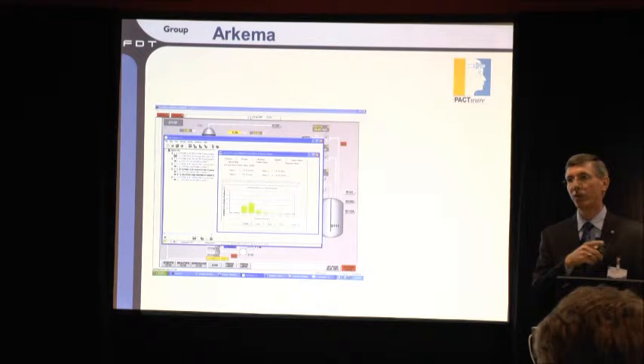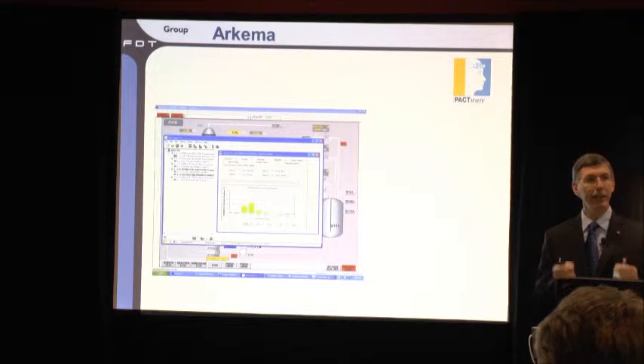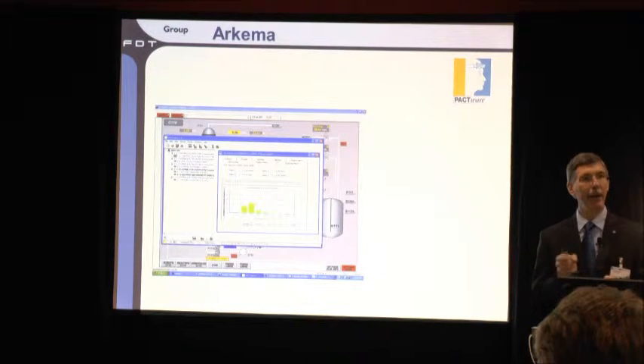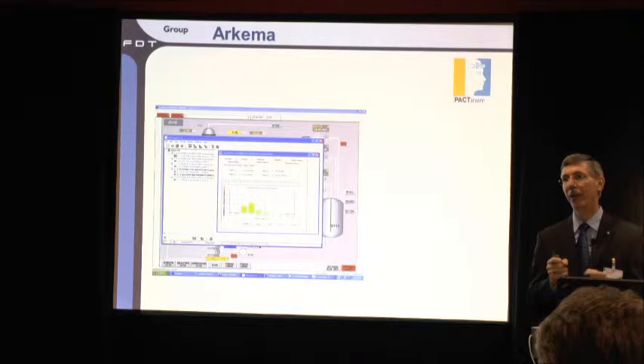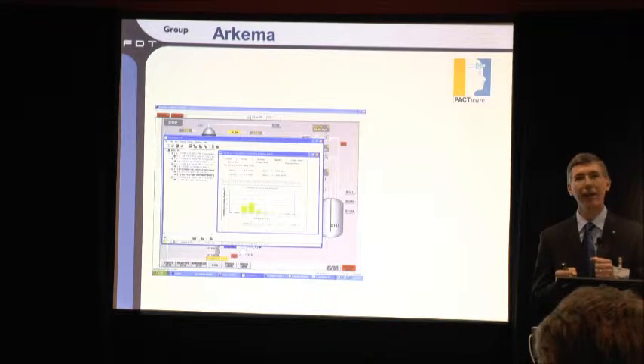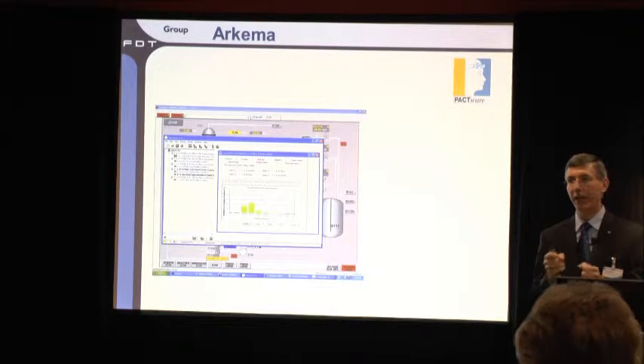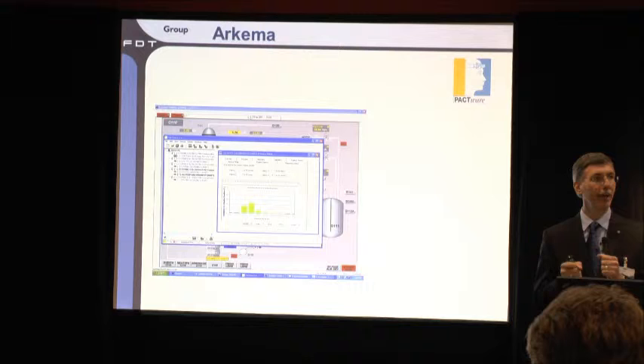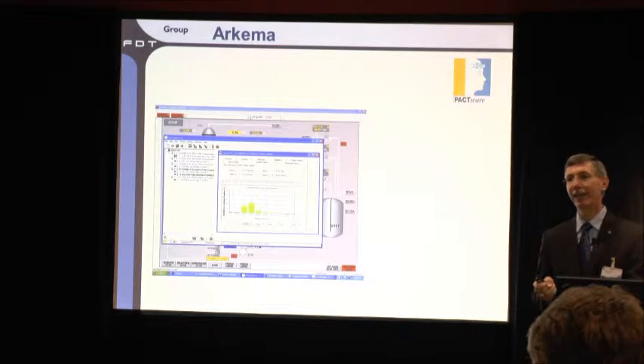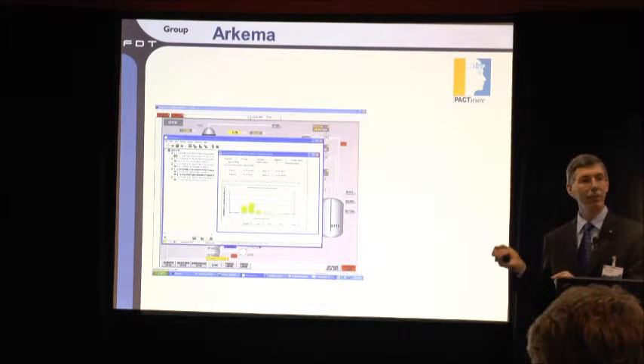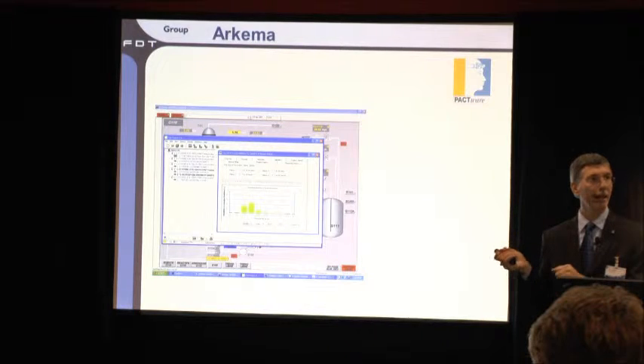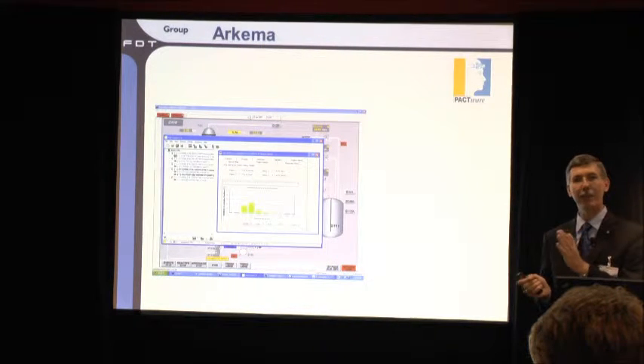As shown in the rotor demonstration, they talked about the torque it takes to open and close a valve and how that changes over time depending on the valve's health. You can trend that information and actually start to predict from the data when it's time to maintain that valve - you don't have to guess or just put it on a calendar and hope you're right. You just look at the data, and it'll show you clearly when the valve is trending towards a maintenance need.